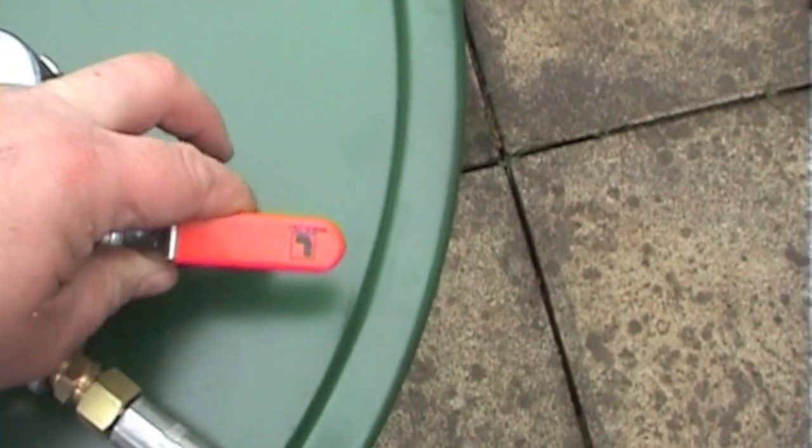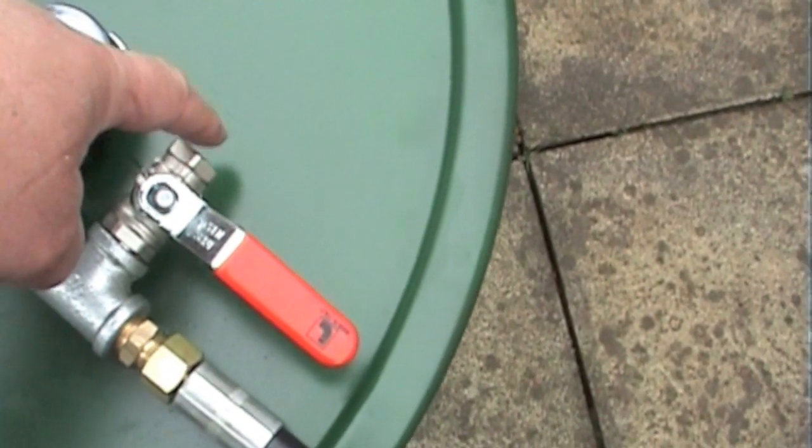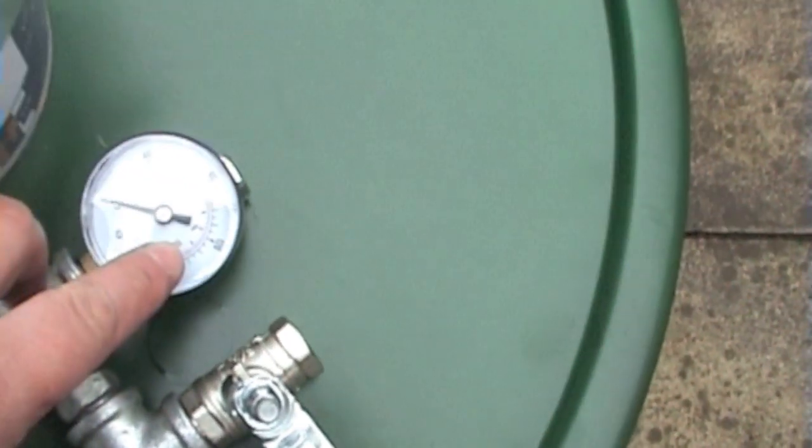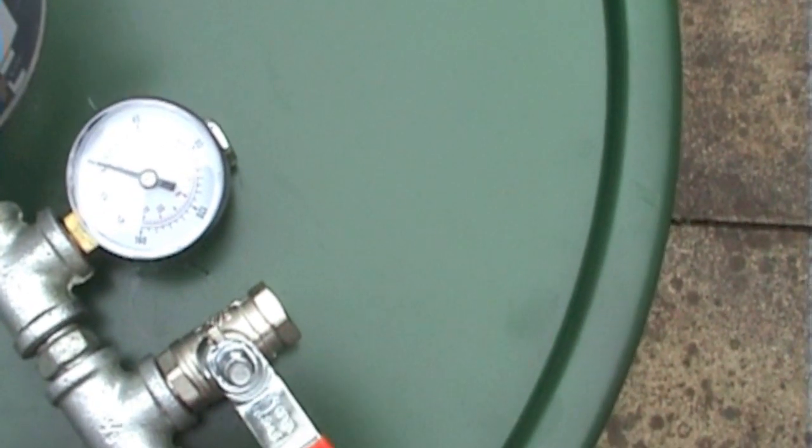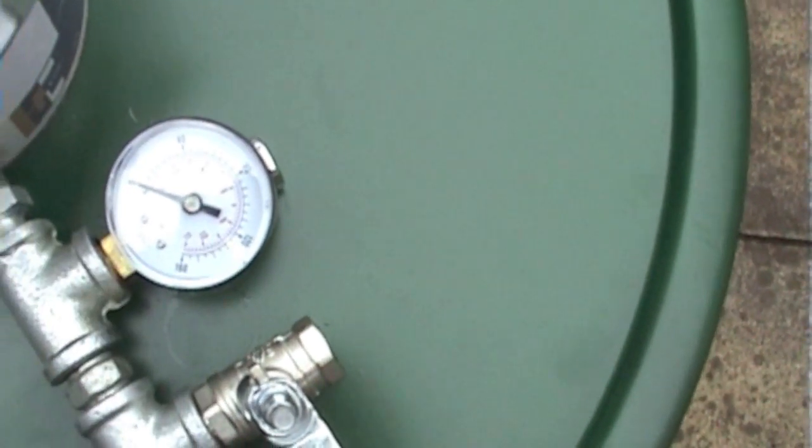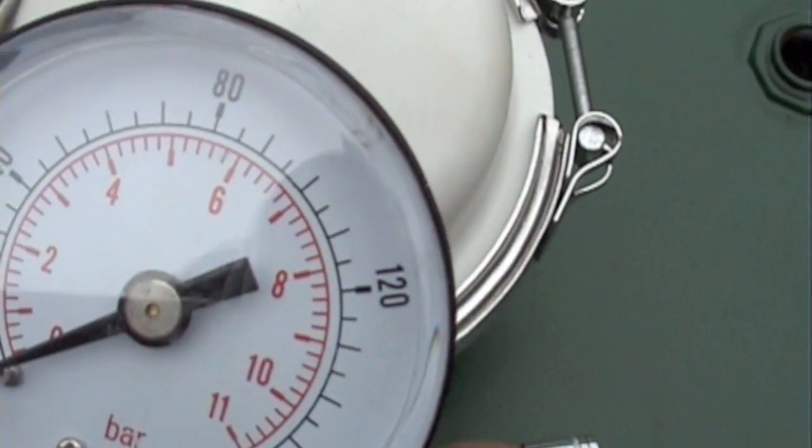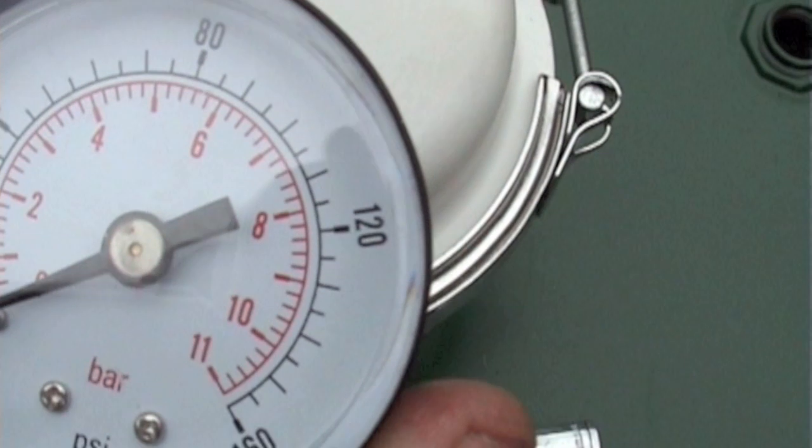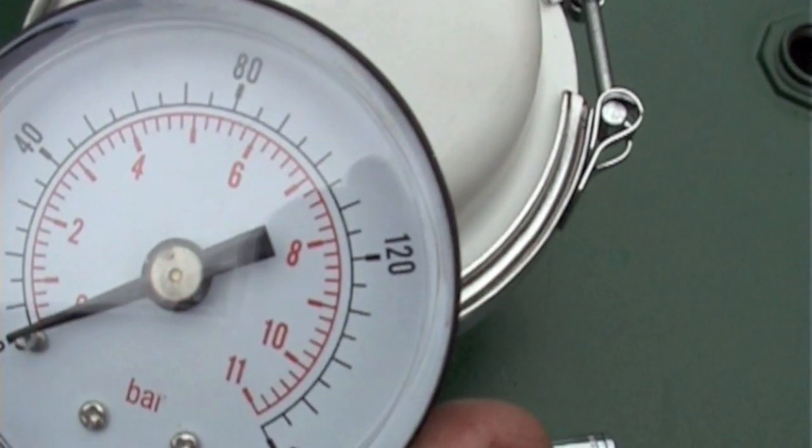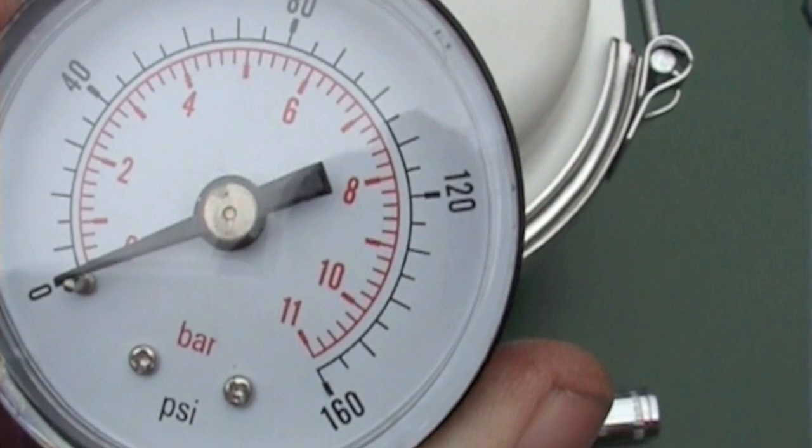So what you'll do, you'll have your overflow pipe coming from here going back into the drum. And when that reads, so you'll have it fully open, close it slowly. And when it reaches nine bars, between the eight and the ten in red, that's your optimal working pressure, nine bars.